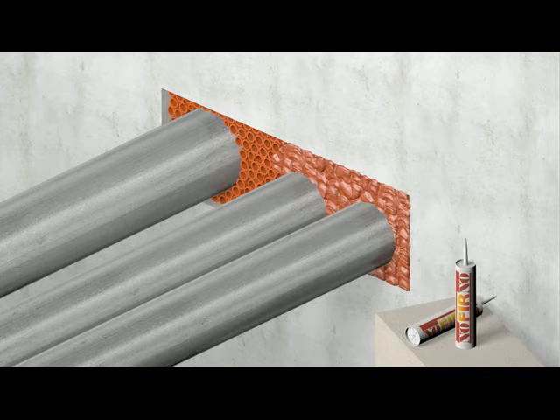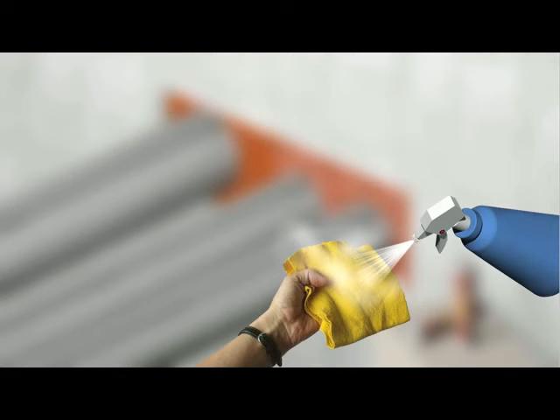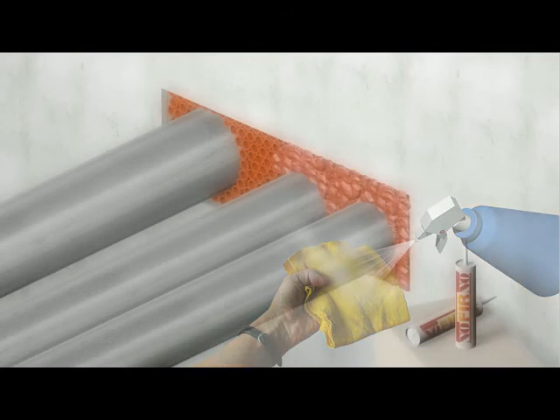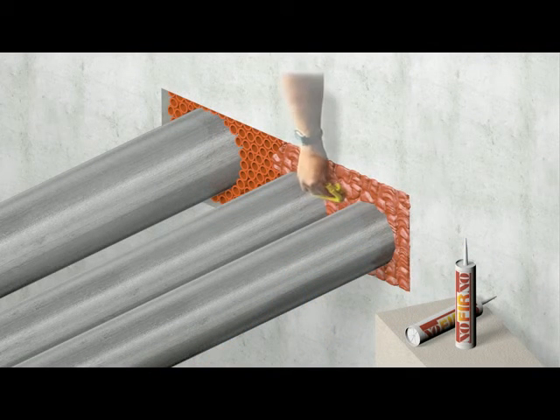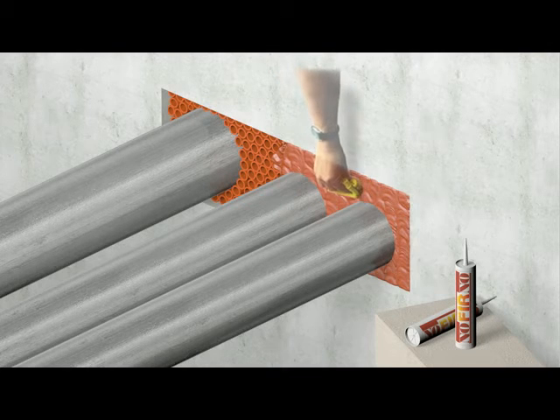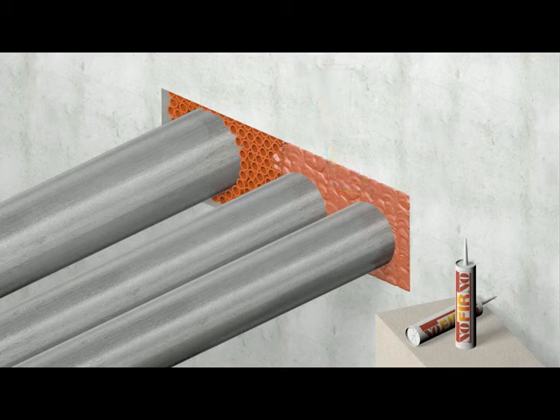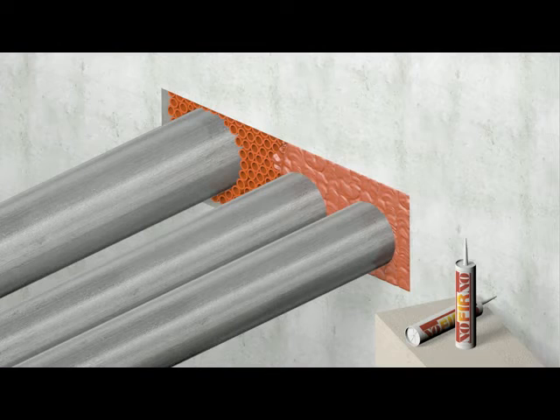To smooth the surface of the Nofirno sealant layer, a cloth is sprayed with water. This prevents the sealant from sticking to the cloth. Do not use soap water. The cloth is then used to press down the sealant layer. Pressing down the Nofirno sealant in a stiff way is absolutely vital for the mechanical stability of the sealing system.